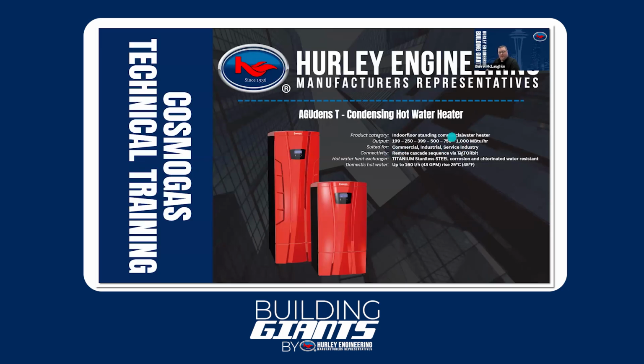There's 6 models because there's actually 2 different heat exchangers. And by that, I mean, we've got a 250,000 BTU heat exchanger. So that if we went from 1 to 2, we go to 500. A third heat exchanger gives us 750, and a 4th one would give us 1,000,000.